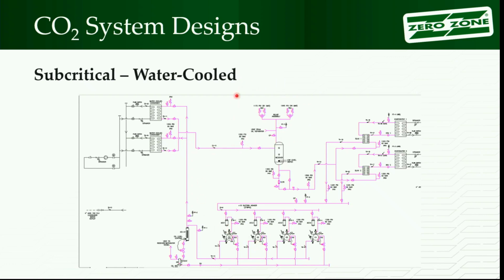This one is the example where we have the regulating relief and the main relief up here showing up on the receiver. This is an industrial system, and they wanted to be able to just turn it off if they didn't have a cooling load on it. So we designed it at 90 bar. All the components in the system are 90 bar. 90 bar is above that transcritical point. So this system you just shut off, walk away. Having trouble with startup, shut off, walk away. You're done for the week, shut off and walk away.